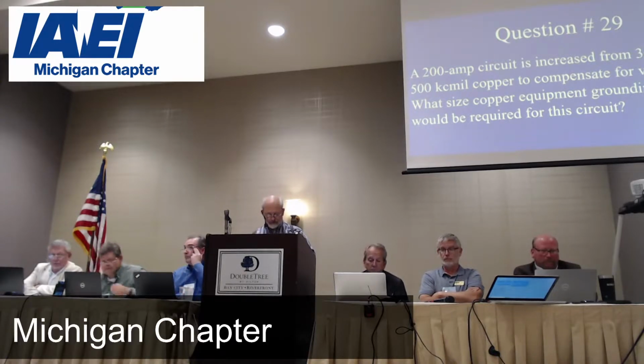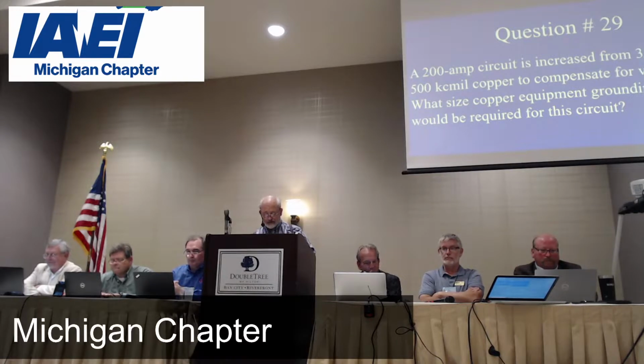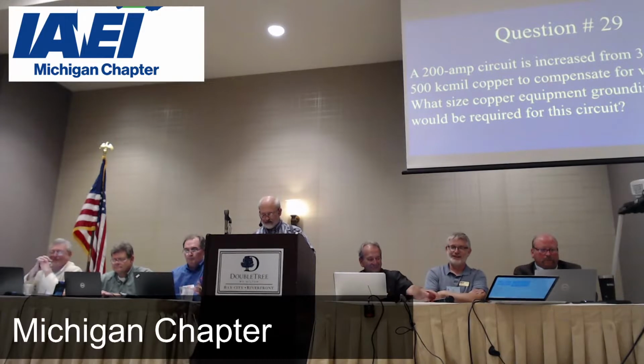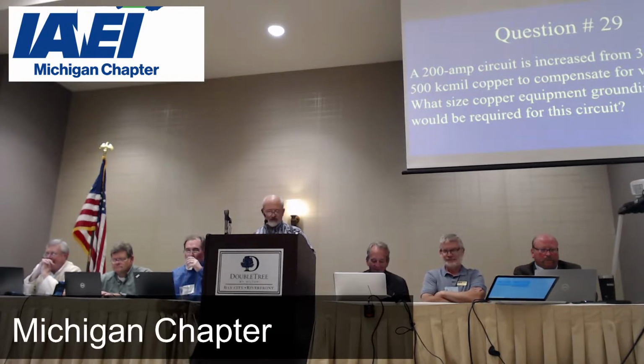Bill? Yeah, you're on. A 200 amp circuit is increased from 3/0 copper to 500 kcmil copper to compensate for voltage drop. What size copper equipment grounding conductor would be required for this circuit? See, now you get your grounding questions. We're back to 250.122 again. In this case, it's 250.122(B), increased in size.